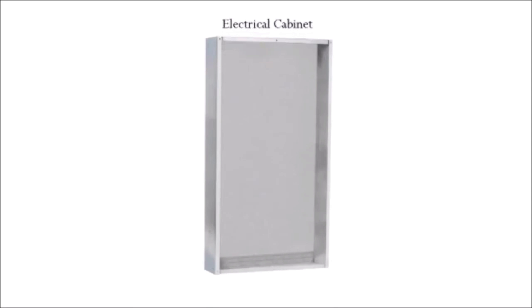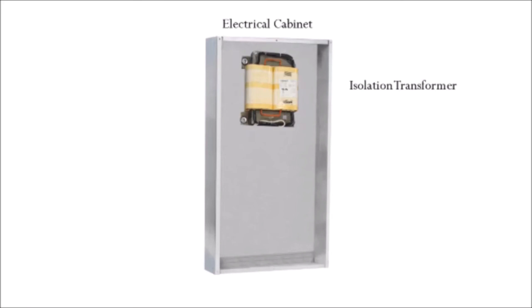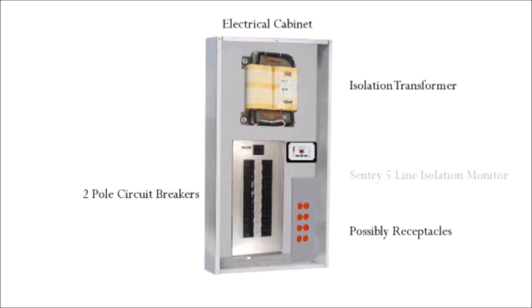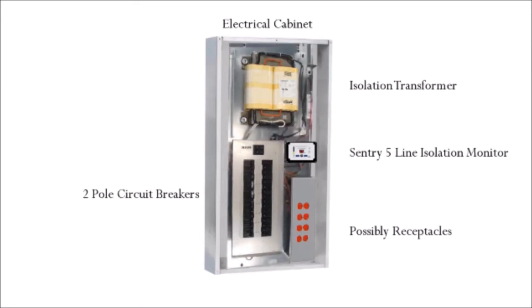Let's look at the components of the isolated power system. Let's build an isolation power panel. First, we need an approved electrical cabinet. The isolated transformer has primary windings and secondary windings. Now we'll add dual circuit breakers to distribute the power. Perhaps we'll add some hospital grade receptacles. And of course, we need the Sentry 5 line isolation monitor to let us know when the leakage to earth ground has exceeded its set point. Now that the components are installed, let's wire it up. We'll finish our isolation power panel by installing the cover.